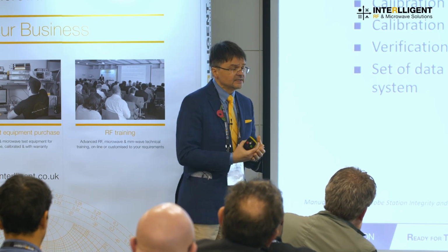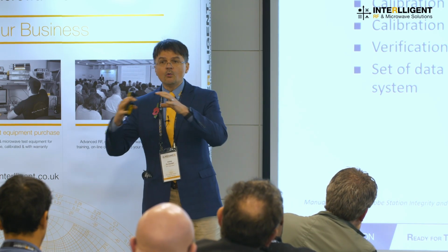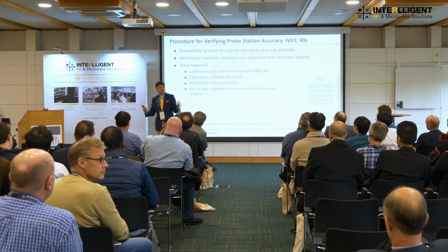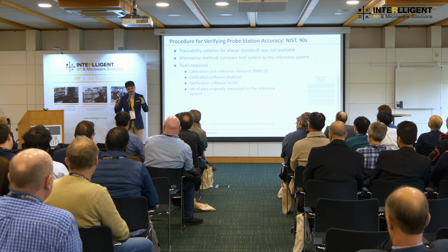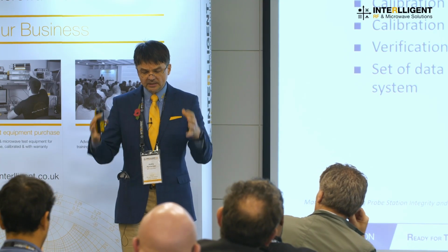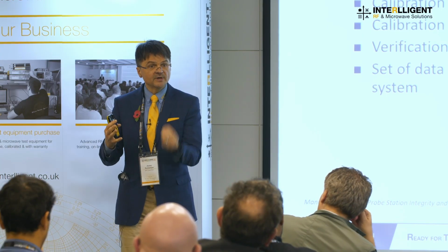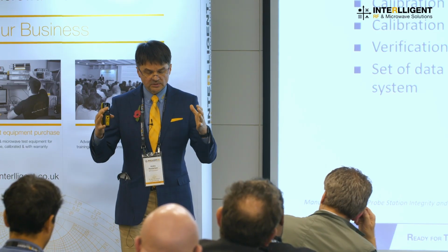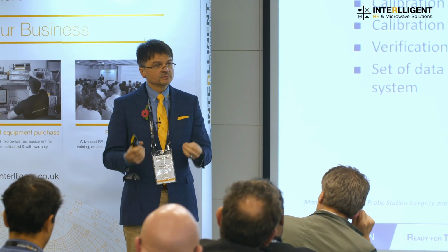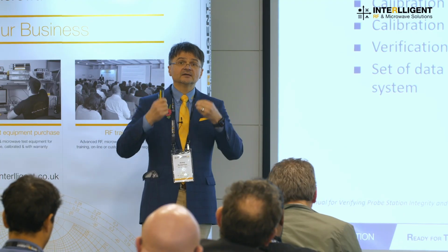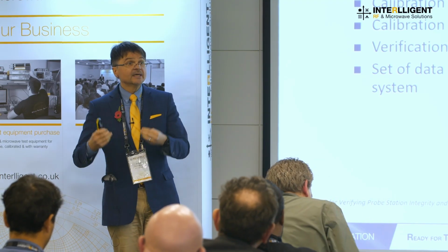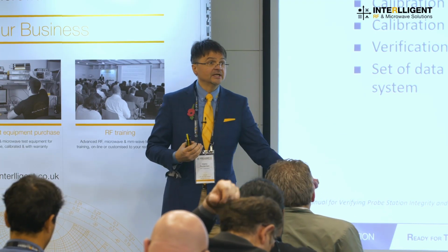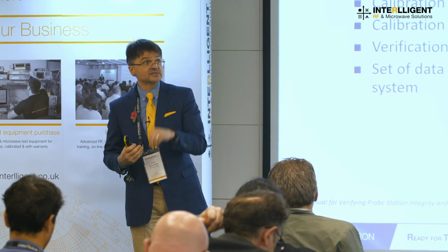And this alternative method helped engineers to compare one measurement setup to another measurement setup and link these two measurement setups together. If we cannot establish traceability for a quantity we measured on one particular measurement setup, we can do our best to complete a measurement set of the data at the maximum possible accuracy we know, and share these measurement results with another partner and help them to correlate their measurement data with our reference measurement setup.